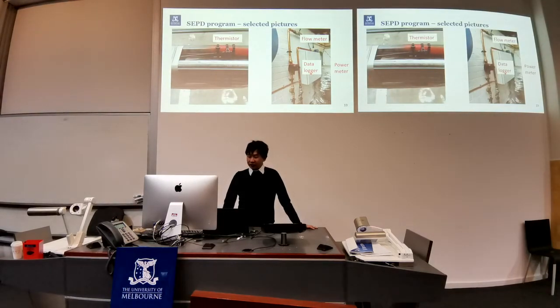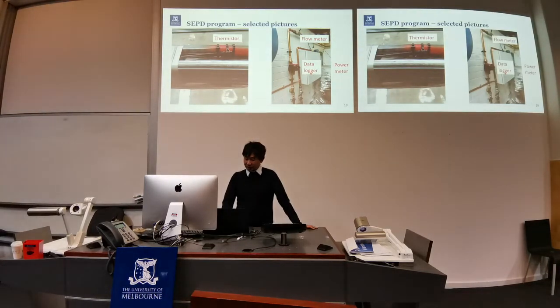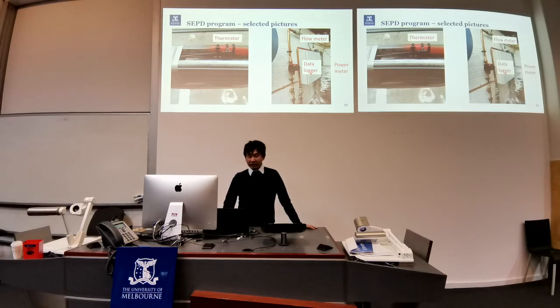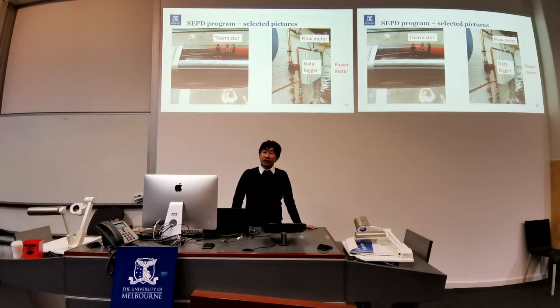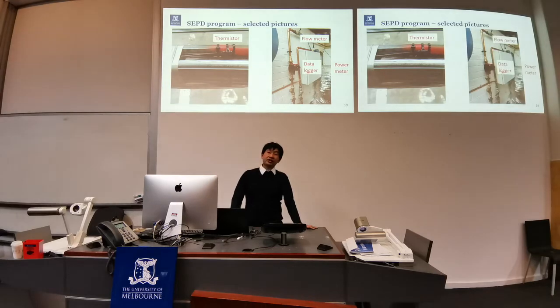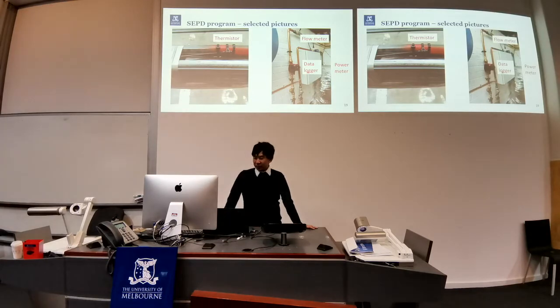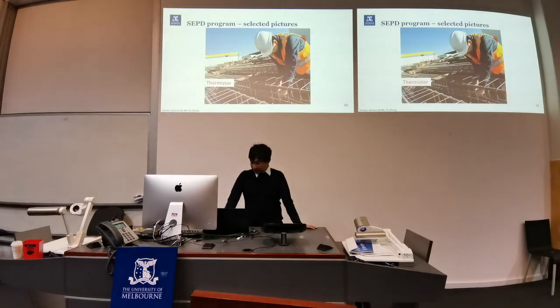Sensors were installed in each of the properties to measure the ground source heat pump system performance. Several thermistors were installed along the ground loop to measure the temperature around the ground heat exchangers. We have a flow meter and thermistor to measure the temperature and flow rate of water going in and out of the heat pump, and a power meter to measure the power consumption of the heat pump itself. Finally, all these sensors are connected to a data logger which can be remotely accessed. Most of the properties were monitored for 3 years.